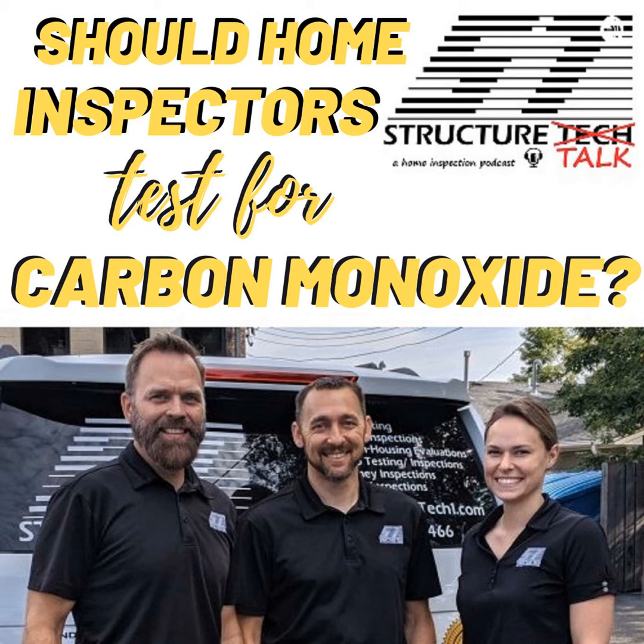And for most of those, it's got to run for 15 minutes. And if the thermostat is still calling for heat after 15 minutes of continuous operation, it's going to go into high fire mode. It's going to go into the second stage. And that's where we want to test it. So when we're dealing with a 2-stage furnace, we definitely want to run it for at least 15 minutes before doing our test.